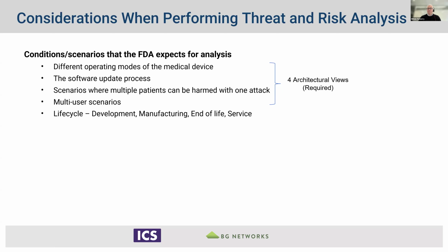Also, the software update process can be somewhat extensive and non-trivial. They want you to consider scenarios where multiple patients can be harmed with one attack, because of the multiplier effect, and that consideration gets a lot of attention, as well as scenarios where there are multiple users on your system. And of course, they want you to consider this not just once the product has been deployed, but across the entire life cycle. That means even while in development, while in manufacturing, and of course end of life and service, et cetera.